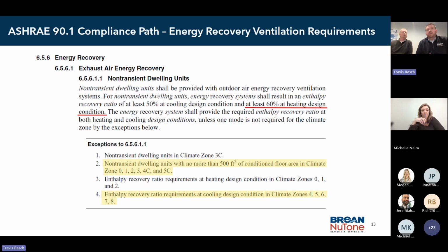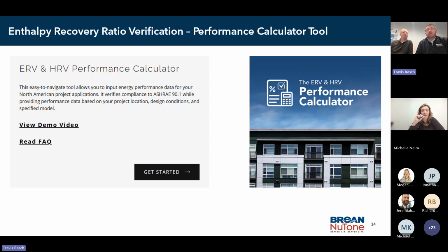The thing to point out here is that value, that at least 60% at heating design, that's for what is an enthalpy recovery ratio. That enthalpy recovery ratio is a calculated value based on the performance of, in this case, an energy recovery ventilator or ERV.